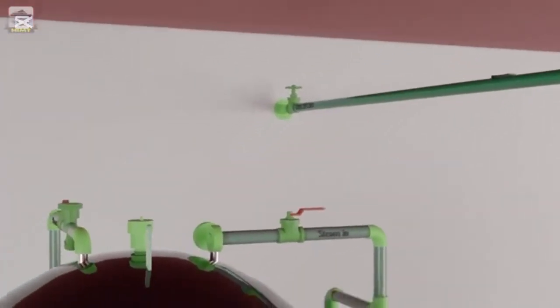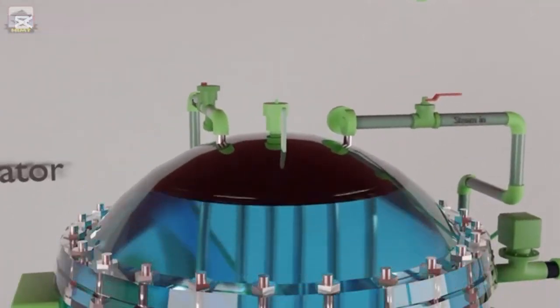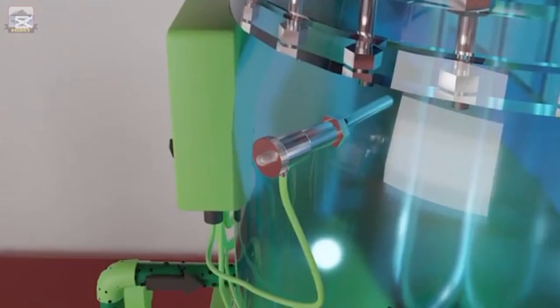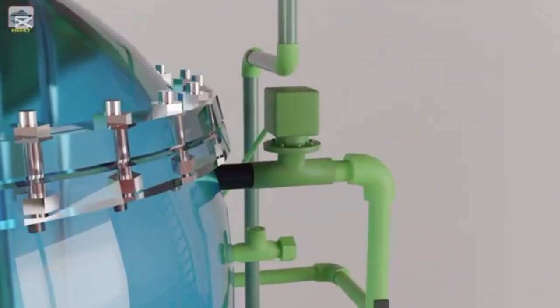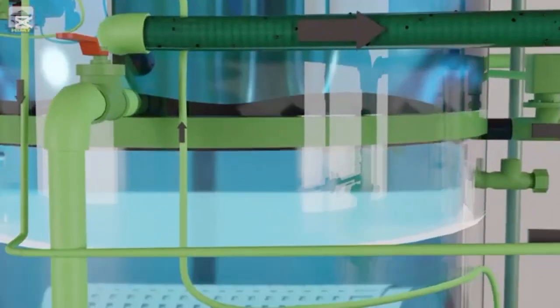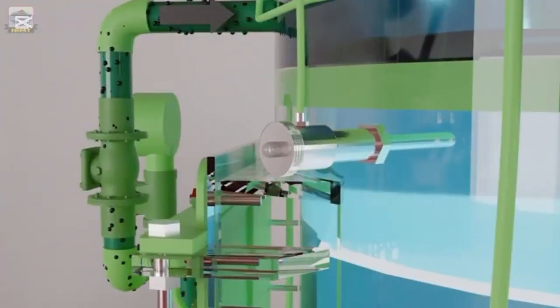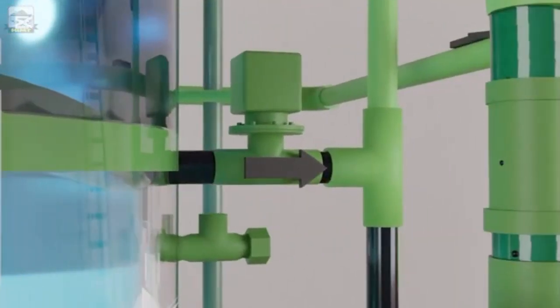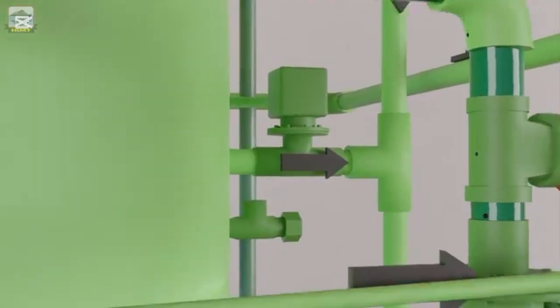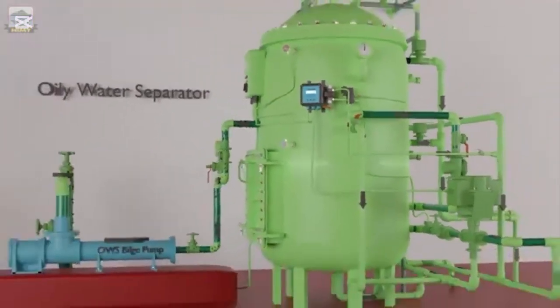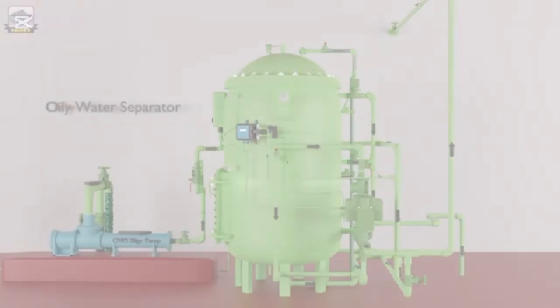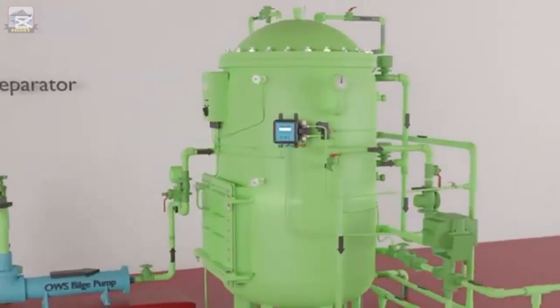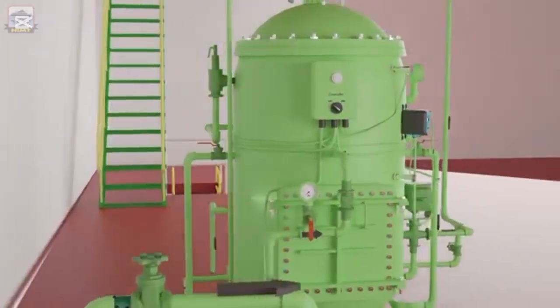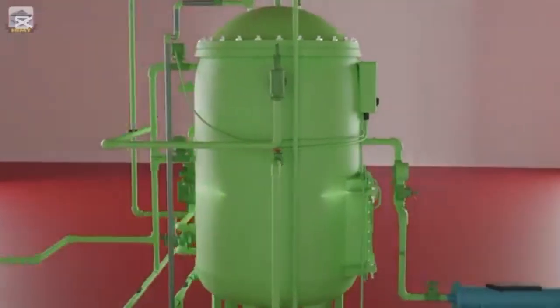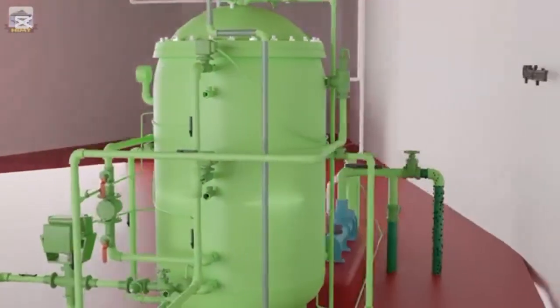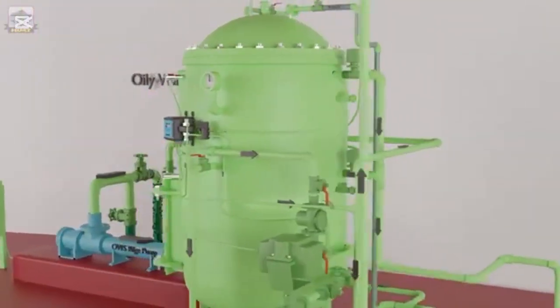If the oil content meter senses over 15 ppm of oil, it closes the discharge to the overboard. Once the oil content is below 15 ppm, discharge resumes to the overboard line. Oil collected in the bottom chambers is then drained, and the outlet closes when the process is completed. Thank you, and that's how an oil water separator functions.